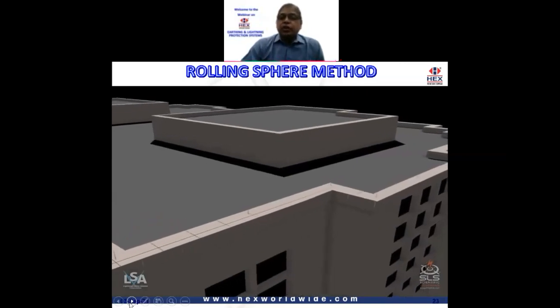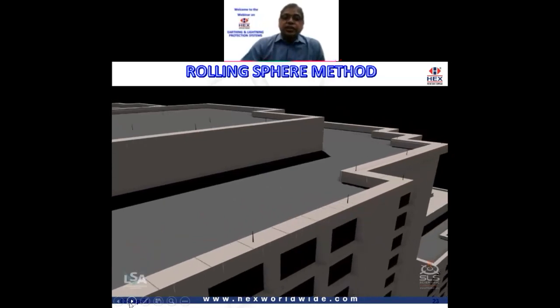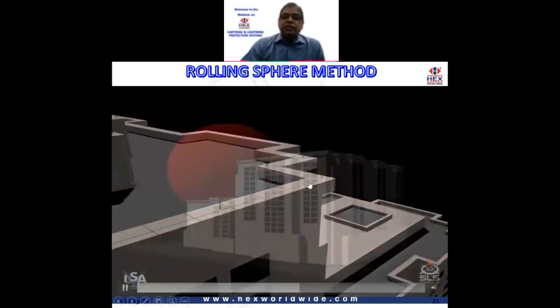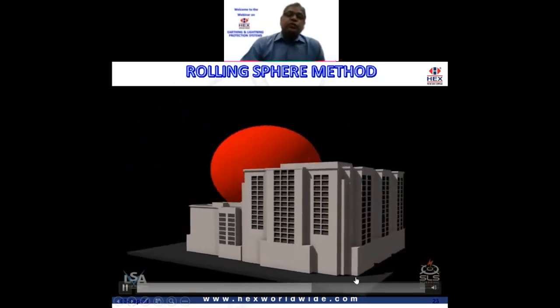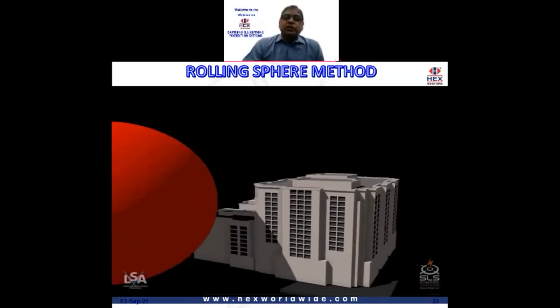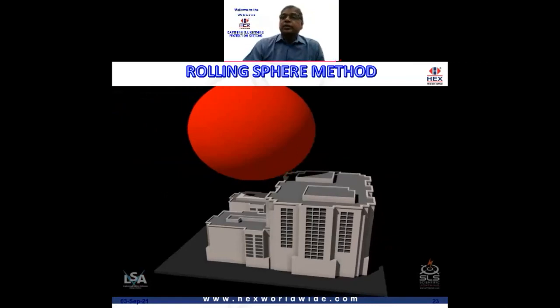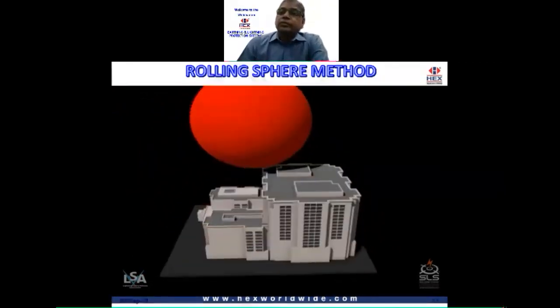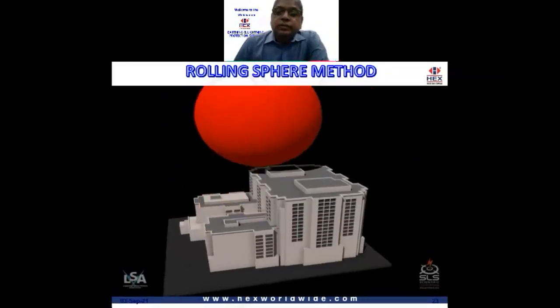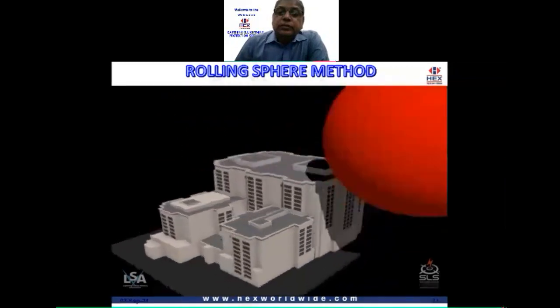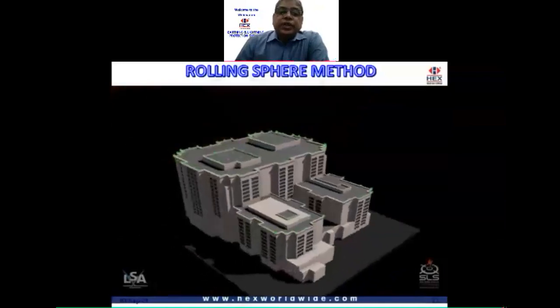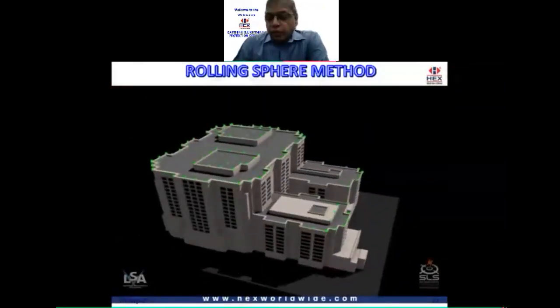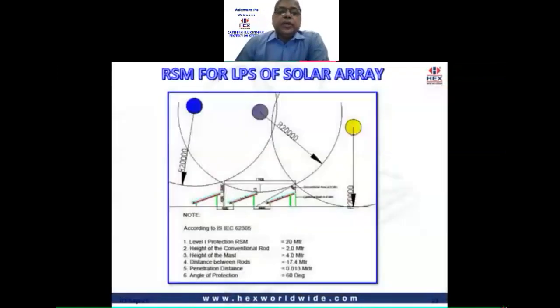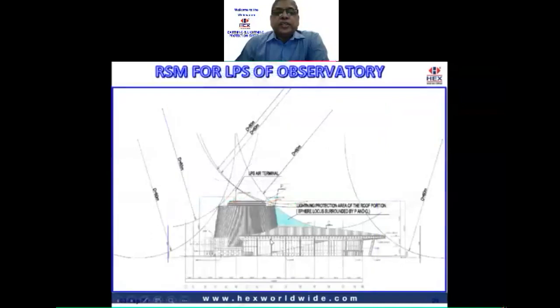Now, as you can see, we have installed the lightning arrestors, the conventional lightning arrestors. We can see them all over as per the lightning protection system design. And then once that is done, when we roll the sphere once again, we can see that everything is turning from red to green. Can you see that? Everything is green now. So this structure has been protected by using the rolling sphere method. We used the rolling sphere method to design protection for a solar array from lightning strikes. Another drawing shows where we used it for protecting an observatory, just to give you some examples.